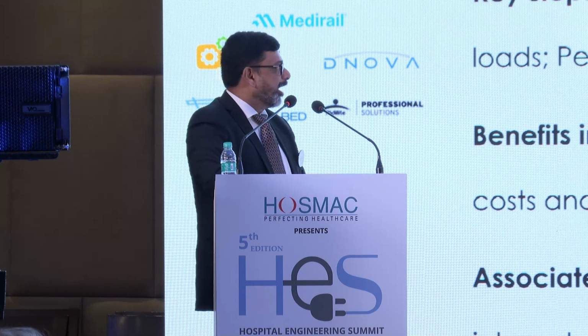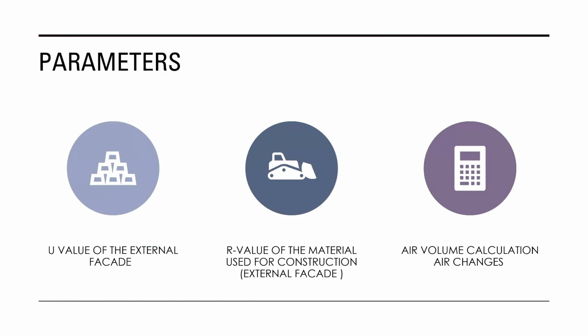Standards come into play here - ASHRAE 90.1 and ASHRAE 170 are essential documents for doing these ventilation calculations for the HAP calculations. The major parameters required for HAP calculations are multiple. I'll go segment by segment to explain this. One is the R values and U values required for the external facade of the building, and the air volumes for internal space calculations.